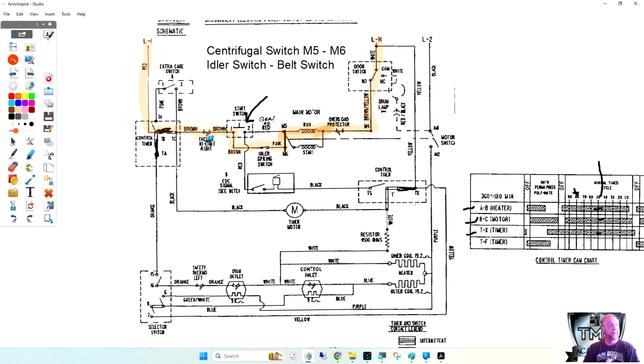And we highlighted the power and how it goes through all the parts. The next thing you want to do is you want to identify the parts that send power to your motor, besides the motor itself. If any one of those parts are bad, the motor don't work. So you have to use the diagram to identify the parts, and then you have to use the meter to test those parts.